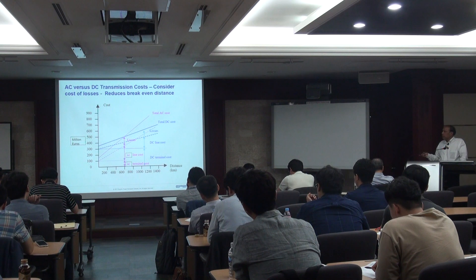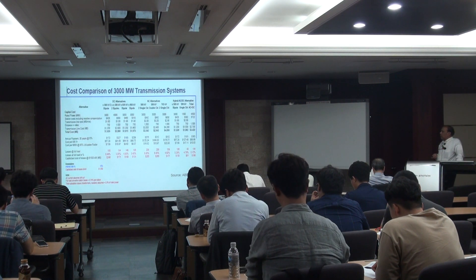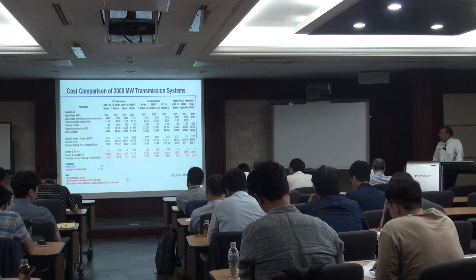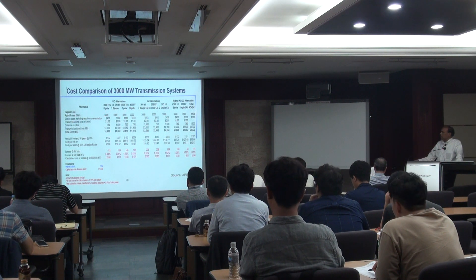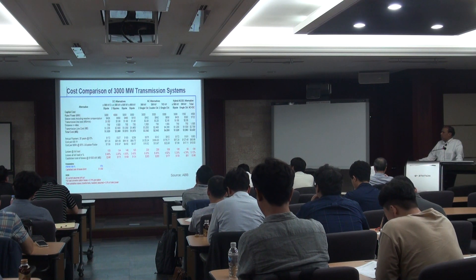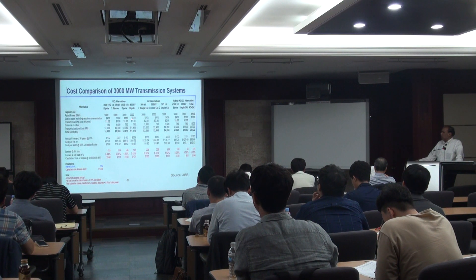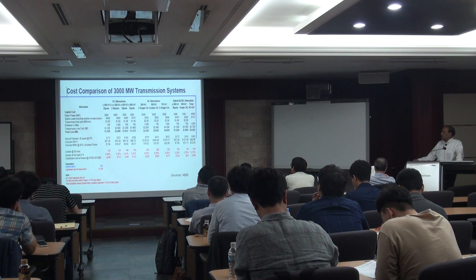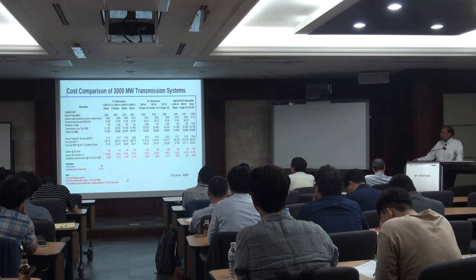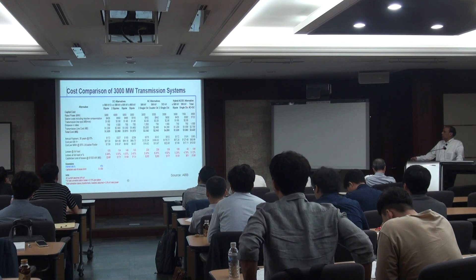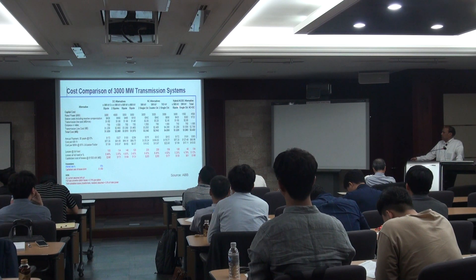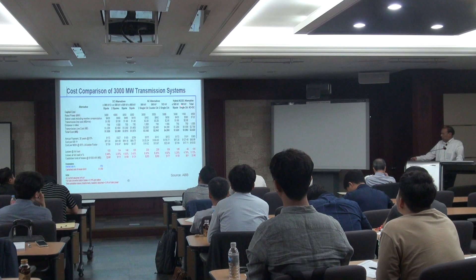An ABB study analyzed DC alternatives: a ±500 kV bipole at 3000 MW, two ±500 kV bipoles at 4000 MW, a ±600 kV bipole at 3000 MW, and an ±800 kV bipole at 3000 MW. AC alternatives included two single-circuit 500 kV lines, a double-circuit 500 kV line, or two 765 kV single circuits — all with roughly the same power rating except one configuration at 4000 MW.